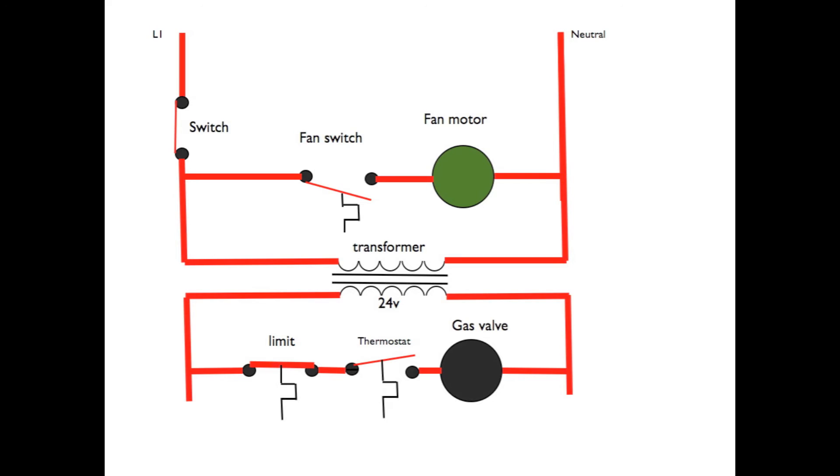With the system switch closed, you can see that's the only switch I've closed. That passes power up to the fan switch, and the fan motor has power going through it. The fan motor is not running because the fan switch is open.